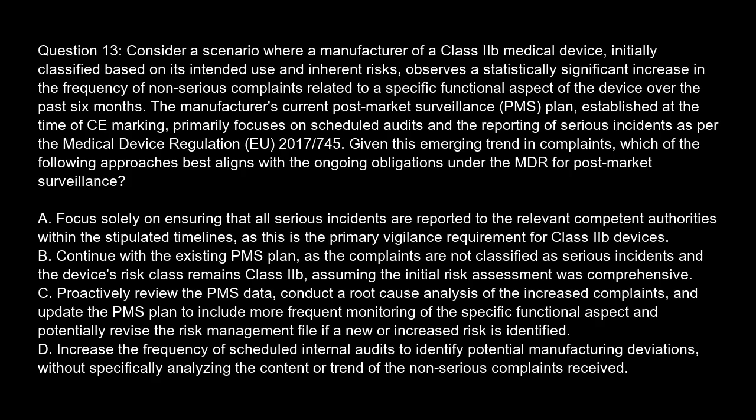2017/745. Given this emerging trend in complaints, which of the following approaches best aligns with the ongoing obligations under the MDR for post-market surveillance? Option A. Focus solely on ensuring that all serious incidents are reported to the relevant competent authorities within the stipulated timelines, as this is the primary vigilance requirement for Class IIb devices. Option B. Continue with the existing PMS plan, as the complaints are not classified as serious incidents and the device's risk class remains Class IIb, assuming the initial risk assessment was comprehensive.